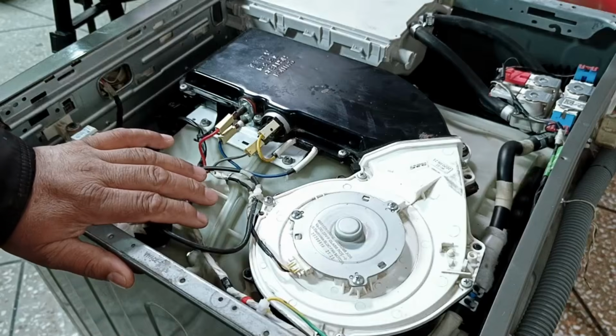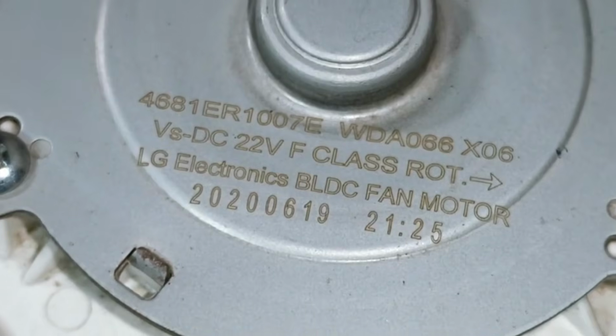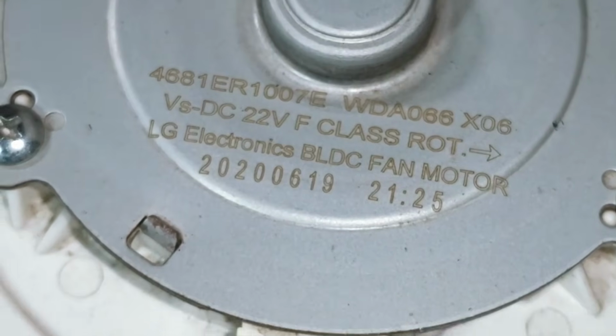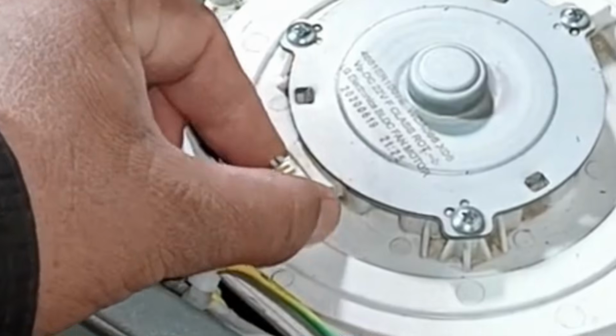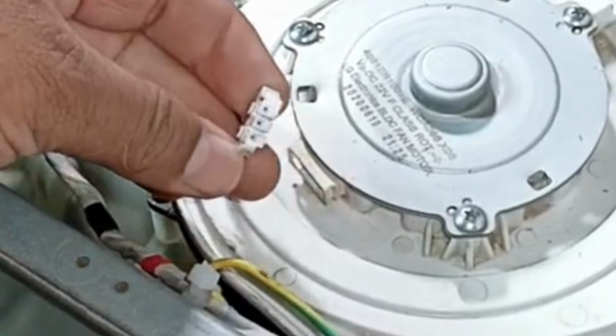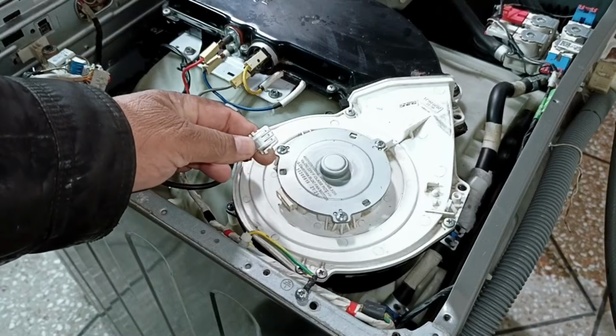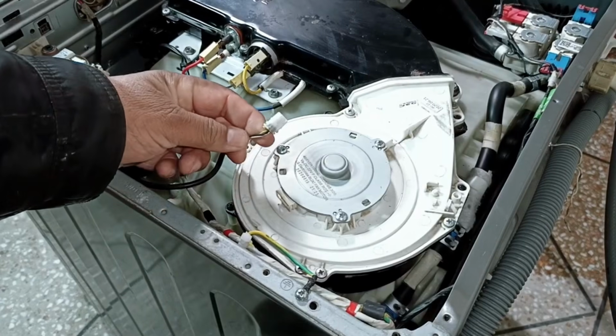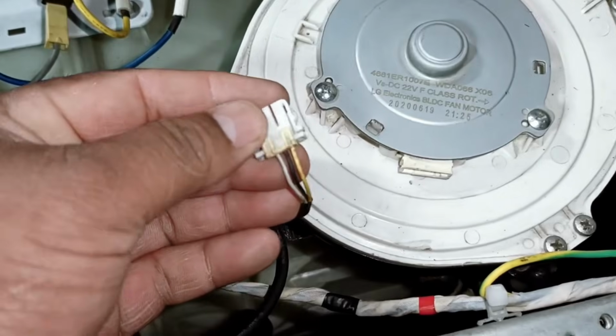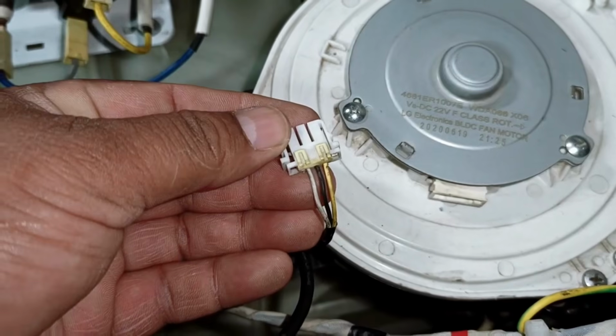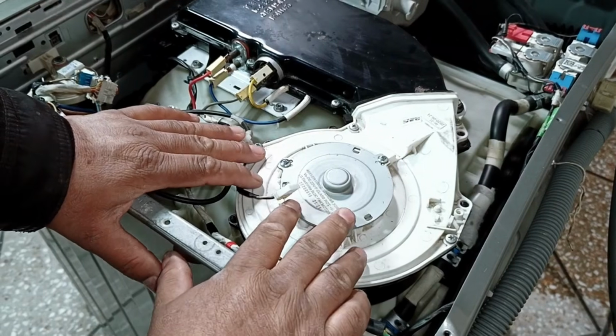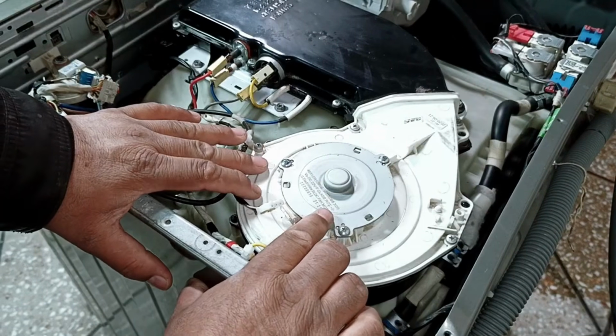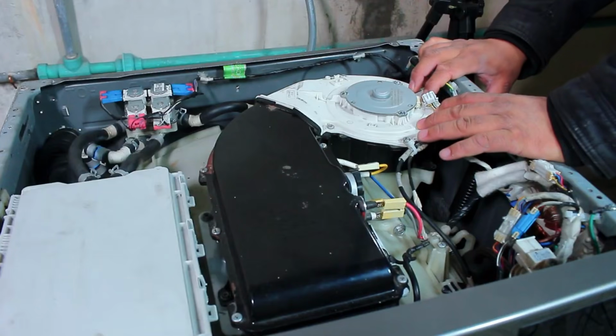Now, if we look at this motor, it operates on 22 volts DC, and this is a BLDC motor. If, for any reason, its connector is loose, disconnected, or if the wiring is damaged, the problem can occur. As you can see, it has 3 wires, black, white, and yellow. If any of these wires are cut or not properly connected, the fan motor will not circulate air properly, and that can also cause this issue.